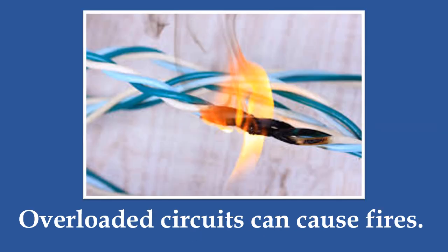It is very important that the conductors not carry more current than its design capacity. A circuit that is unprotected or becomes overloaded due to inadequate overcurrent protection, the fuses and breakers, can lead to smoking, melting conductors, and potentially fire.